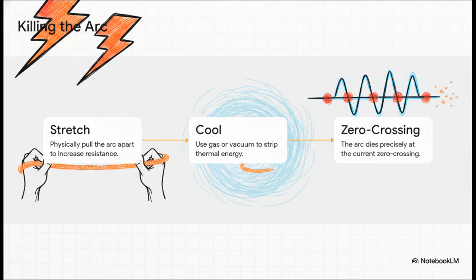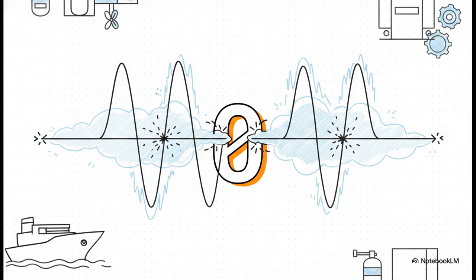First, it stretches the arc, literally pulling it apart physically to increase its resistance. Second, it cools the arc, usually using insulating gases like SF6 or a vacuum chamber to strip away its thermal energy. But here's the crazy part. The arc doesn't actually die from stretching or cooling alone. It dies at step 3, precisely at the alternating current's natural zero crossing. Zero, that is the magic number.